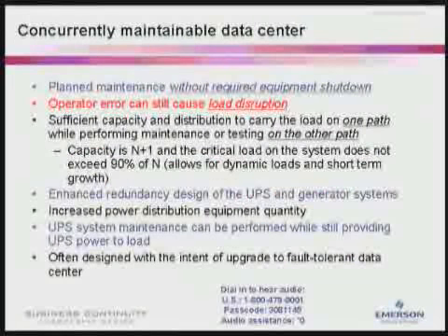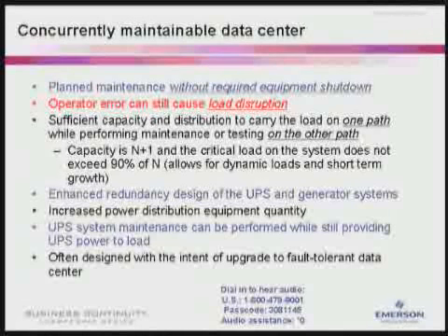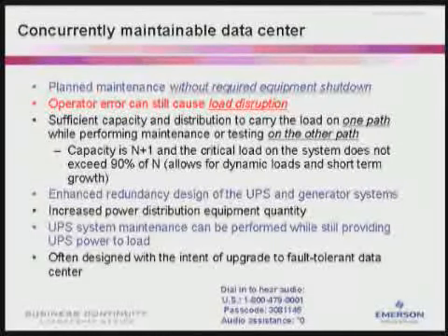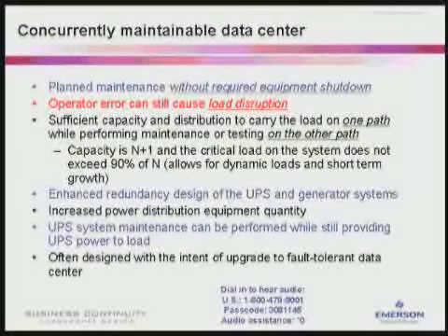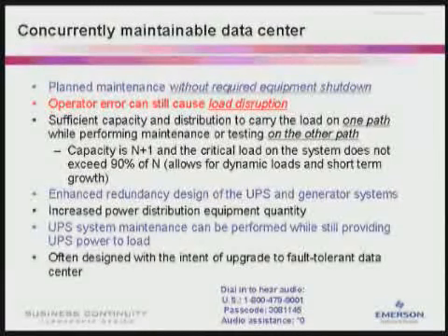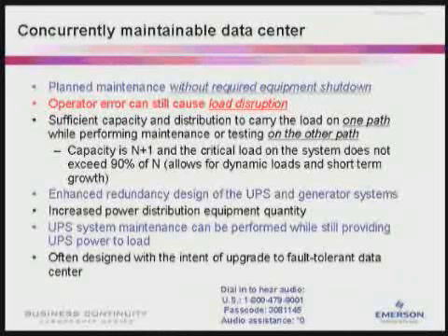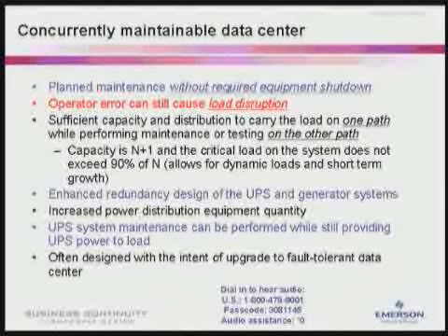Slide. In a concurrently maintainable data center, planned maintenance can be performed without required equipment shutdown. It has enhanced redundancy design of the UPS and generator system. Typically, the capacity is N+1, and the critical load on the system does not exceed 90% of that N. UPS system maintenance can be performed while still providing UPS power to the load. In this case, operator error can still cause load disruption.